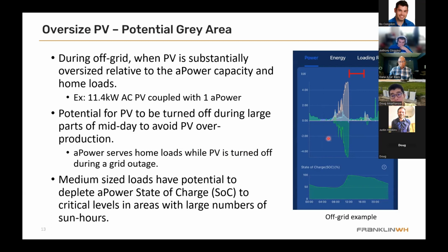So the batteries act as a reservoir to soak up the load. You can see them charging to soak up the PV here, and the PV production ramping up. Home loads are low, and someone's probably getting ready in the morning, then they leave the house for a bit. The home loads are very low, basically just the phantom load of the TV being turned off. The PV will remain off for a portion of the day and then restart later on. It restarts every 20 minutes — you can kind of see those ripples there.